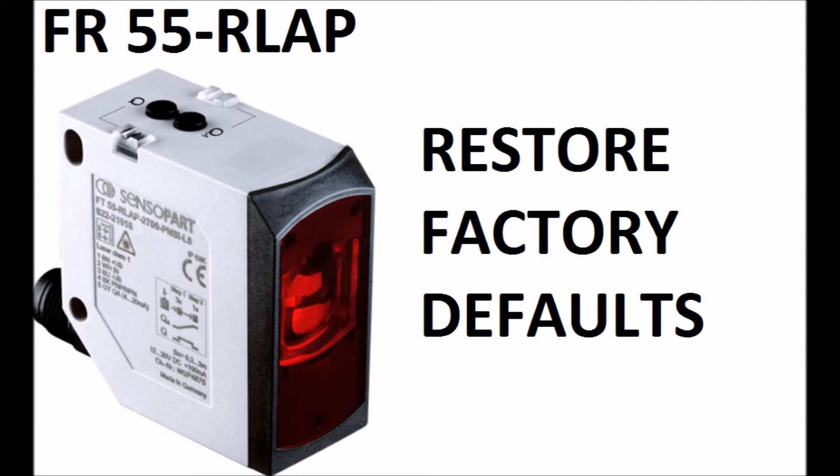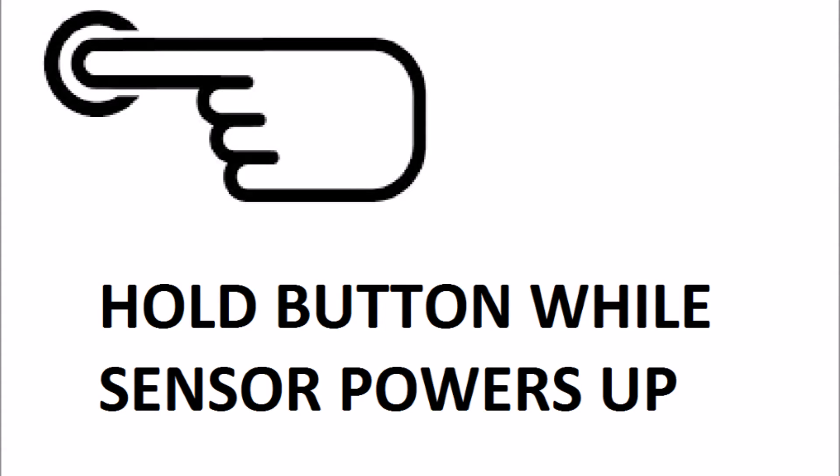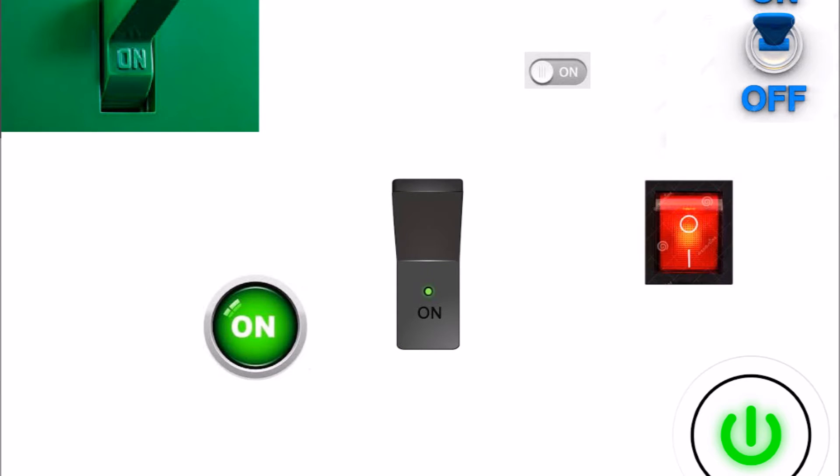To restore the sensor to factory defaults, it takes three steps. First, you turn off power to the sensor. Second, you press and hold any button, or you could energize the PLC output. Third, you power up the sensor while holding the button, and after a few seconds, the lights will flash rapidly, indicating it's been restored to factory defaults.